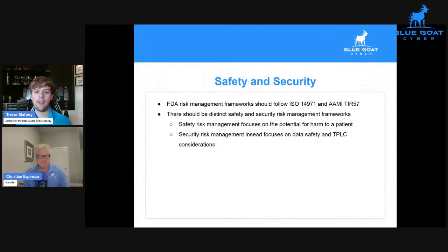Despite the fact that these are separate, it's pretty easily apparent how there can be some overlap here. If there is a problem with data safety or TPLC consideration that can introduce a vulnerability into a medical device, that is very often going to introduce harm into a patient. So having a clear distinction between these two processes, but also a little bit of a way for them to bleed into each other, can be pretty important to make sure that we're covering everything as far as safety and security overlap. These two risk management frameworks are very similar from their flow. TIR57 is based on 14971, and so it's pretty apparent reading through the process that they follow. It's just more focused on a different outcome.